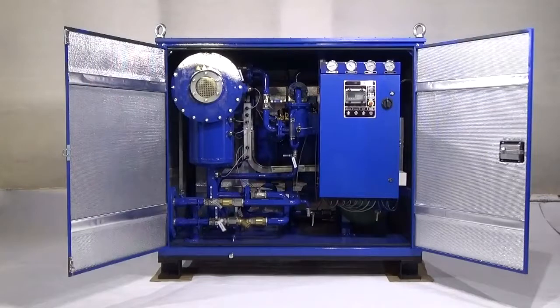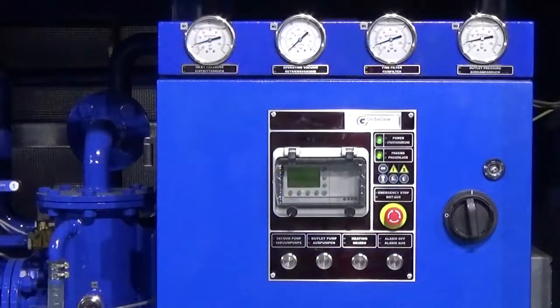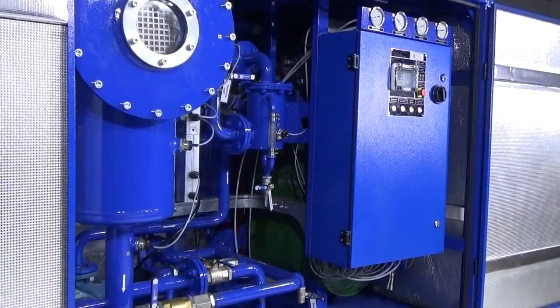7. Control the vacuum in the system as indicated by the operation vacuum gauge. If the oil is highly contaminated, vacuum may cause foaming of the oil. In this case, air will enter the unit through the air inlet electromagnetic valve, reducing vacuum in the system. In this case, process the oil in several cycles.